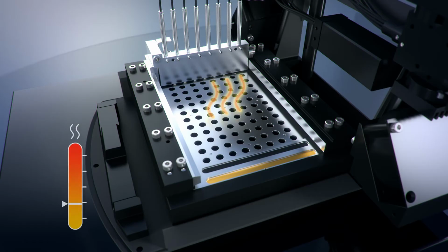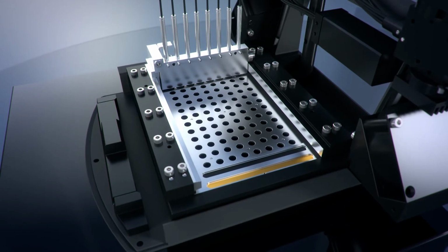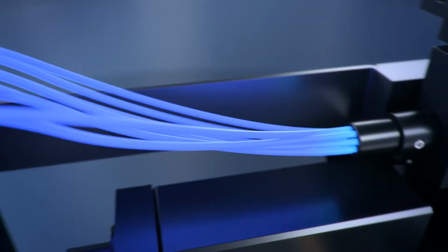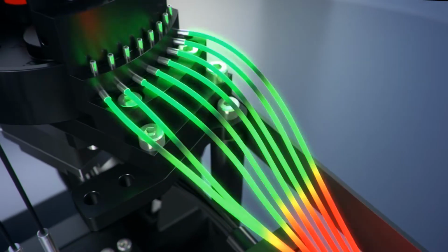To avoid any condensation and sample loss, the system is equipped with a motorized heated lid. Temperatures are adjustable up to 110 degrees Celsius, with an even contact pressure guaranteeing optimal performance independent of the consumables used. The heart of the patented highly sensitive fiber optics is a unique light source.